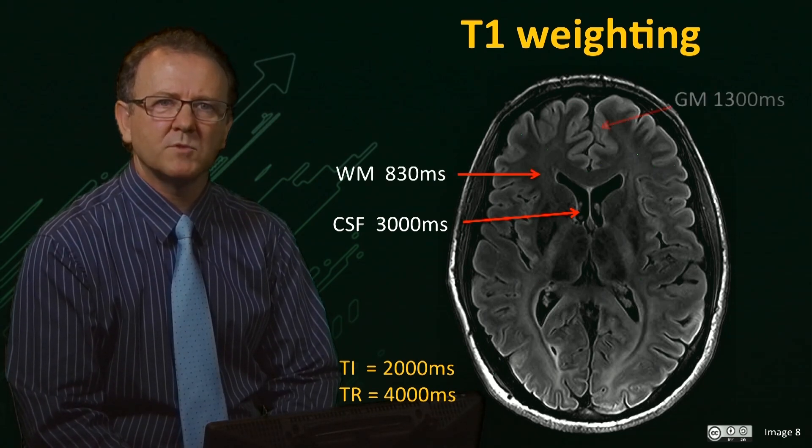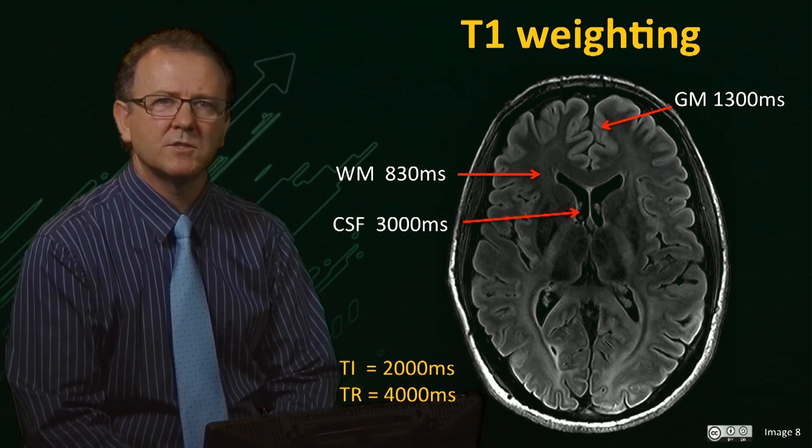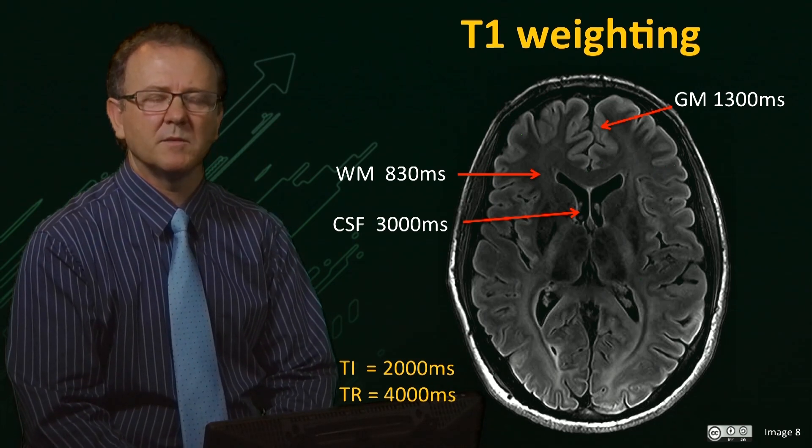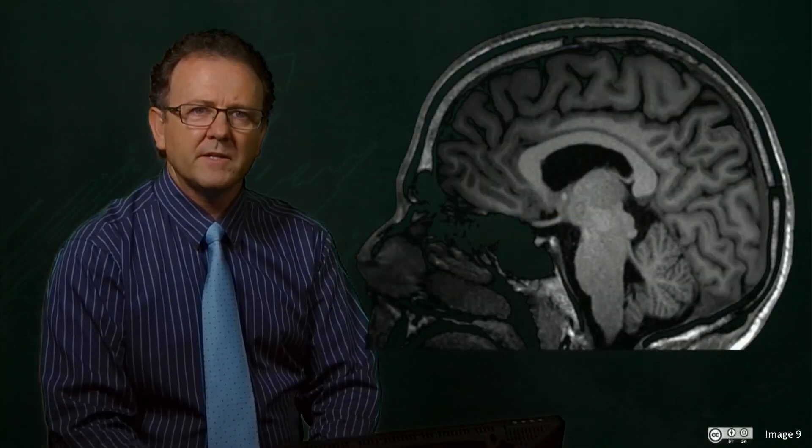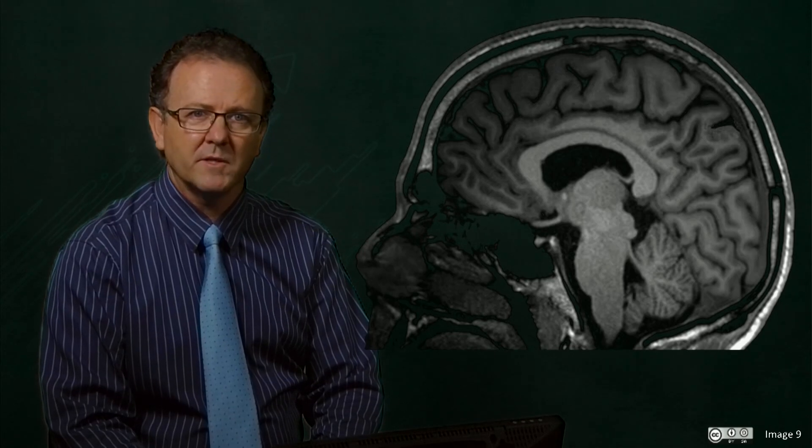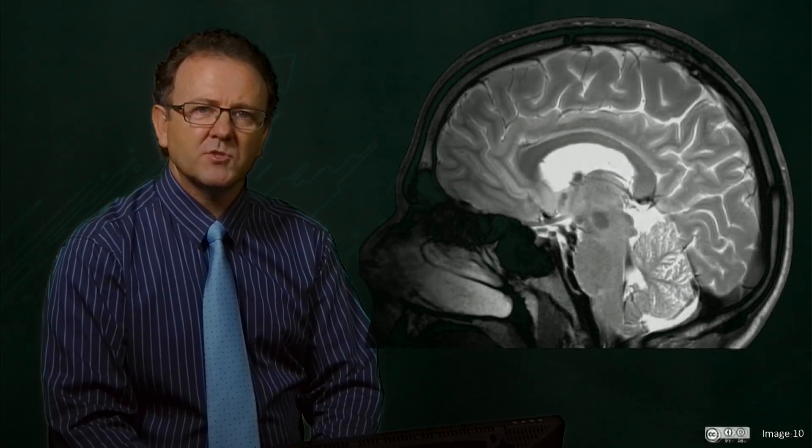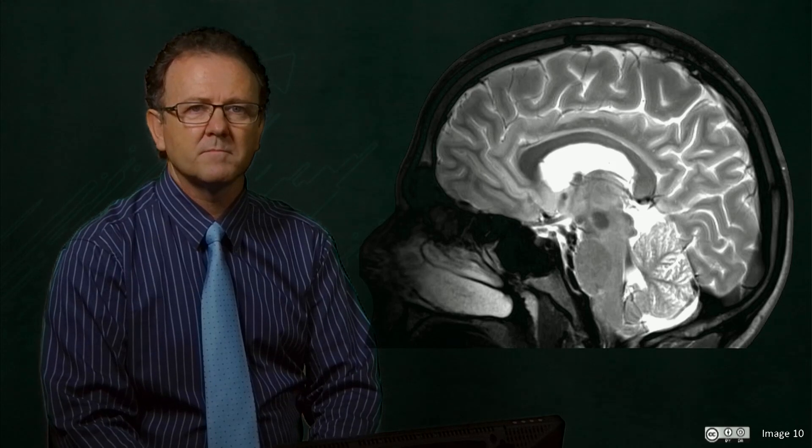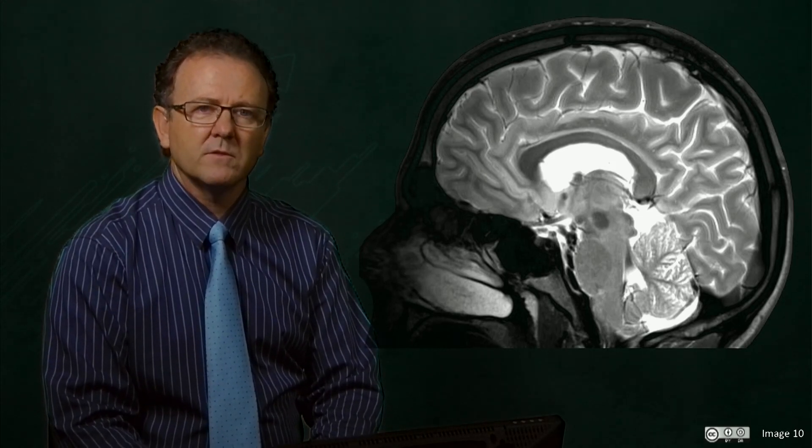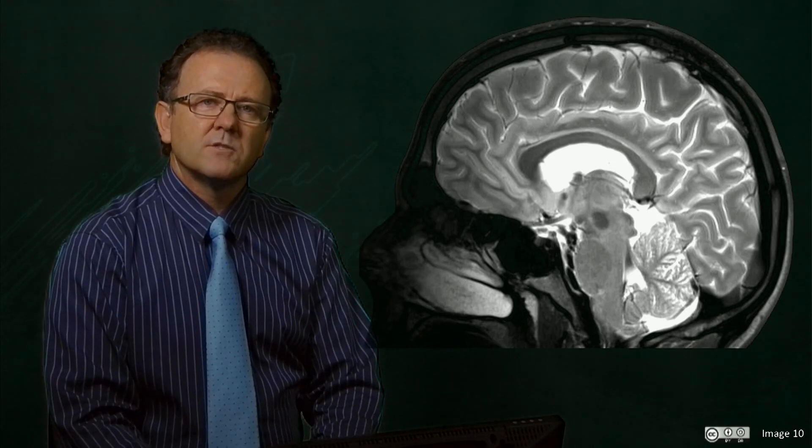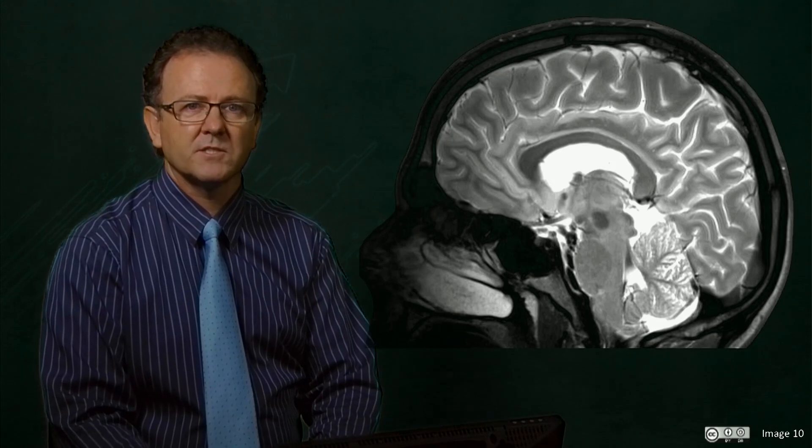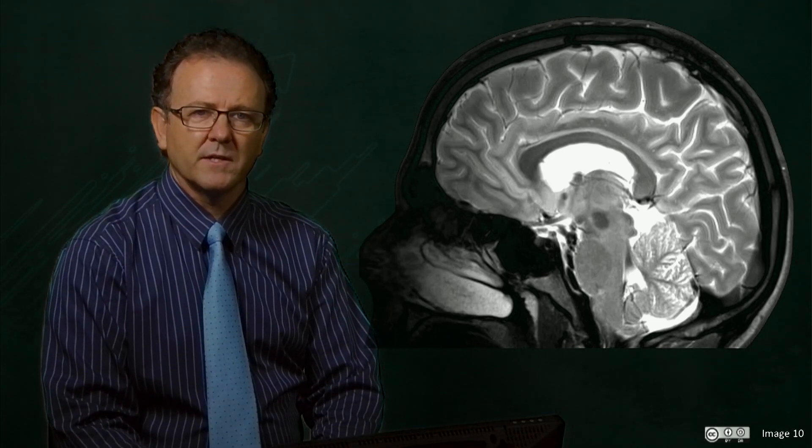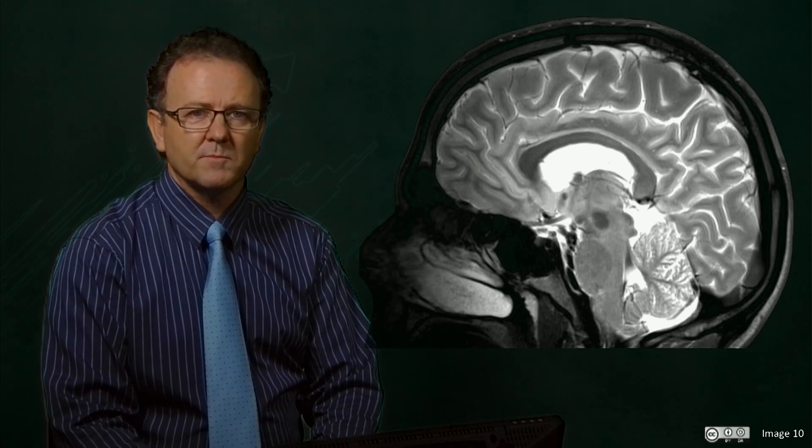So we now have a means by which we can manipulate the relative signal intensities of tissues and enhance the image contrast. Here we see a complete inversion of the image contrast between an inversion recovery T1 image and a T2 weighted image, demonstrating that the same tissue can produce totally the opposite signal intensity depending on the sequence and parameters chosen. We can exploit the relaxation properties to brighten or darken particular tissues. So if a structure in the body appears dark, it does not necessarily follow that there is little or no water present. Most of the MR imaging sequences used in the clinic today are designed to produce contrast based on the principles of relaxation.